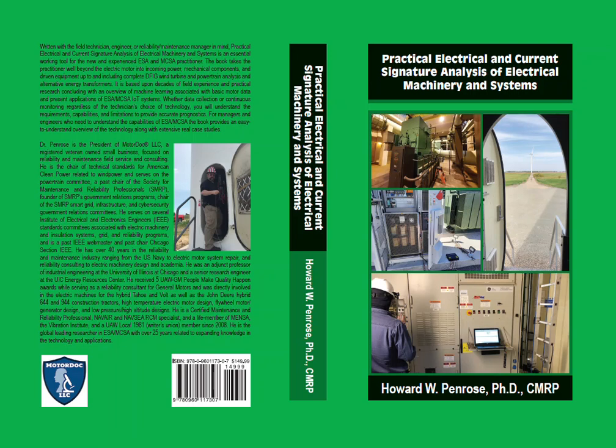Over the next few years, we had repeated situations where disagreements between the repair company and customers were occurring due to misdiagnosis using MCSA technologies. Each time I would have to perform research into what was being detected and how it was being detected, and started to notice how and what the technology was doing. The challenge was that the resolution was not very good, and it would require at least 50 to 75% loading of the motor in order to separate peaks from power harmonics.